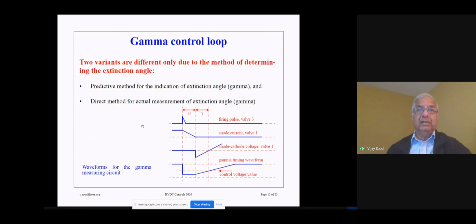So here is the direct method. You can see that when, for instance, the firing pulse for valve 3 is given, that is the point which we need to detect. We look at the valve voltage and we detect when the valve firing pulse is given. We set up a delay circuit over here, and that delay circuit is generated by this angle mu, which is the commutation angle. As soon as the valve 3 firing pulse is given, the current in valve number 1 starts to be taken down. It goes down to 0, and this period for that current to go down from 1 per unit value to 0 is the commutation angle for that valve.